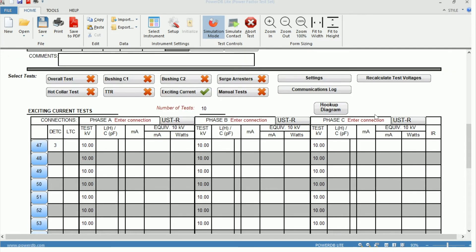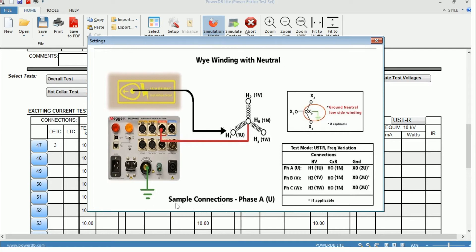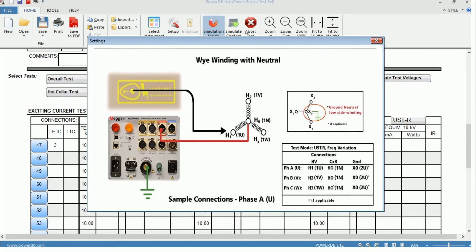We can also see at the top, we have the option for a hookup diagram. In this case, we just have a YY0. And we can see for testing phase A, you have the sample connections where high voltage is applied to your H1 bushing and your measurement lead seen in red is attached to the H0 bushing. And the other phase connections are here, as well, for phase B and C.